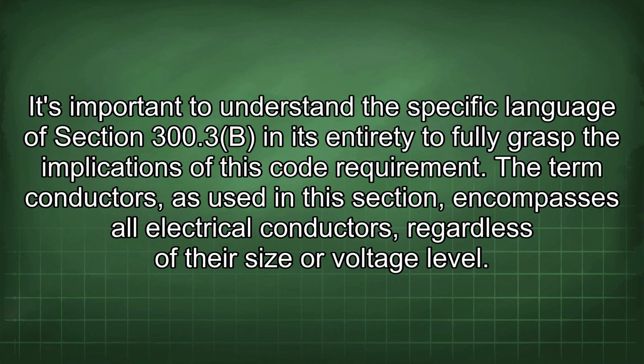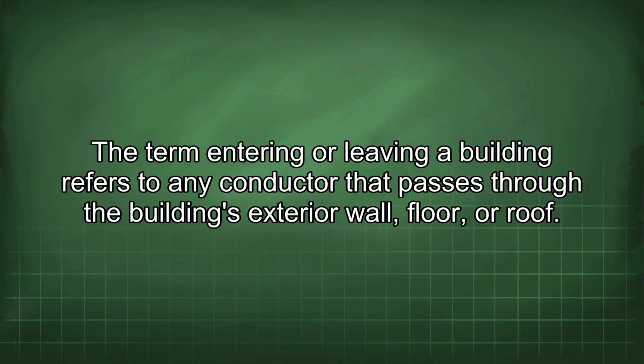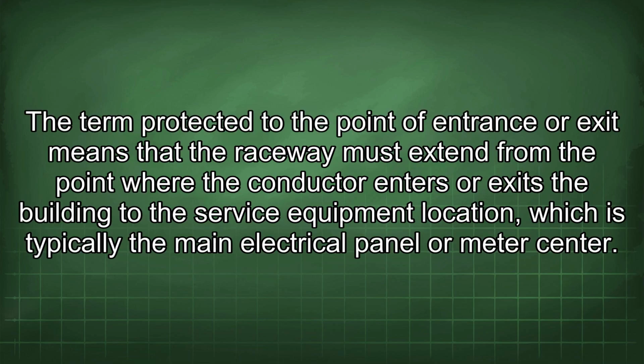It's important to understand the specific language of Section 300.3b in its entirety to fully grasp the implications of this code requirement. The term conductors, as used in this section, encompasses all electrical conductors, regardless of their size or voltage level. The term entering or leaving a building refers to any conductor that passes through the building's exterior wall, floor, or roof. The term protected to the point of entrance or exit means that the raceway must extend from the point where the conductor enters or exits the building to the service equipment location, which is typically the main electrical panel or meter center.